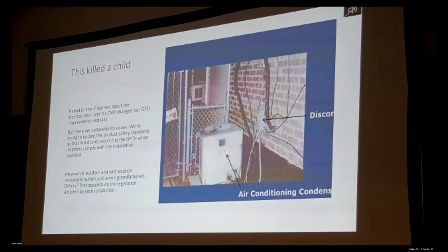My home, they have it. If I'm installing one, it's going to have it. And we're working on it at UL 943. We're working on that issue of expanding the requirements to specify you will not trip below a certain number of milliamps at higher frequencies, and you must trip at certain milliamps. And it's going to depend on frequency because it's a matter of the impedance of the skin, and the higher frequency is supposed to be safer.